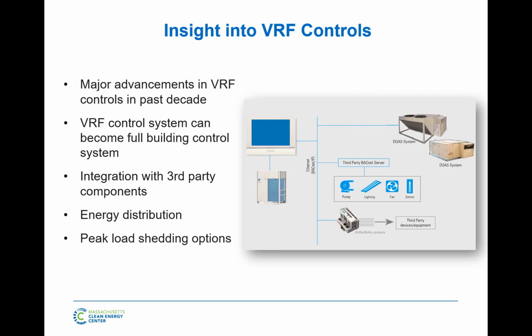What that means is any VRF system that you install, for it to turn on, that condensing unit is going to be wired to all the fan coils, all the indoor units, and you're going to use our thermostats. You can use my thermostats in my system. You can use Greg's thermostat with his systems, because a regular thermostat just doesn't have the intelligence to tell us what we need to run our systems. Even a Nest thermostat is too basic.